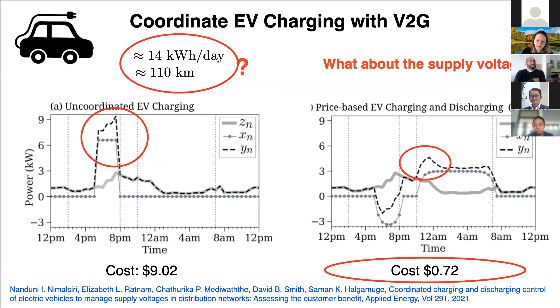But what about our supply voltages? If we just charge and discharge and took away the voltage constraints, we would still have this reduction from 9 kilowatts to 5. So we solve the problem of upgrading, for example, the transformer. But what about the supply voltages?